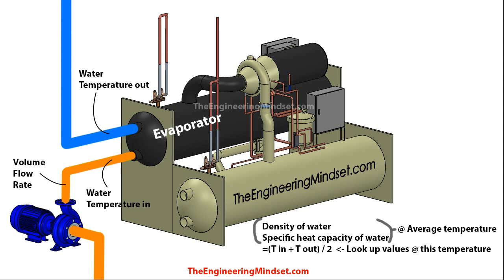There are a few things we need to know in order to perform this calculation. So let's imagine we've got our centrifugal chiller here, with the evaporator located over here and our pump. The return chilled water coming from around the building goes into the pump, which spins it around and pushes it through the evaporator where it cools down, and then leaves and goes off through the building.